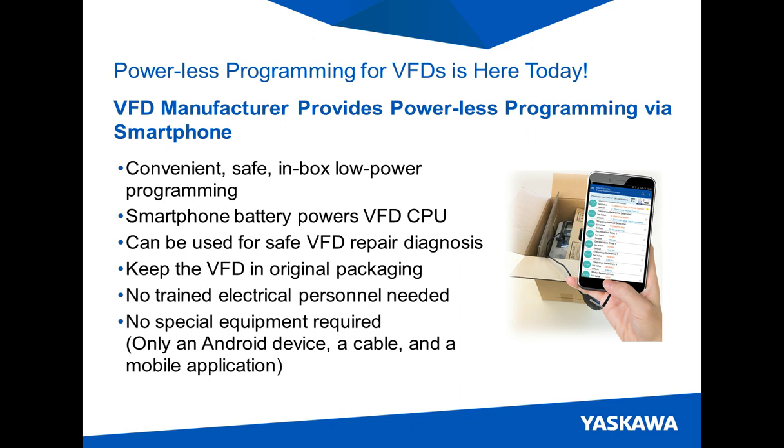And using your smartphone and a mobile app to access those settings with low power is actually safer, more convenient, and it could even be a way to diagnose some failed VFDs returned for repair without having to hook up main power. And again, this keeps the VFD in its original packaging. No special electrical personnel or equipment is needed, only an Android device, a cable, and a mobile app.